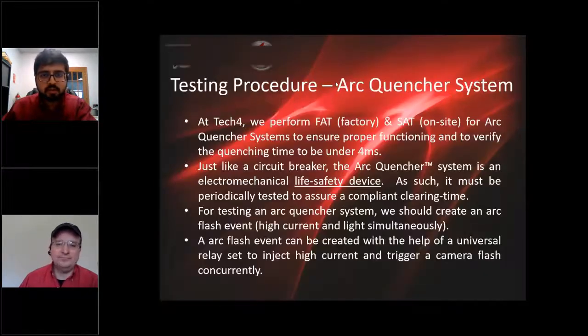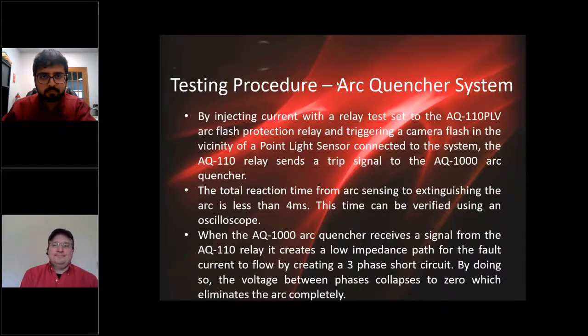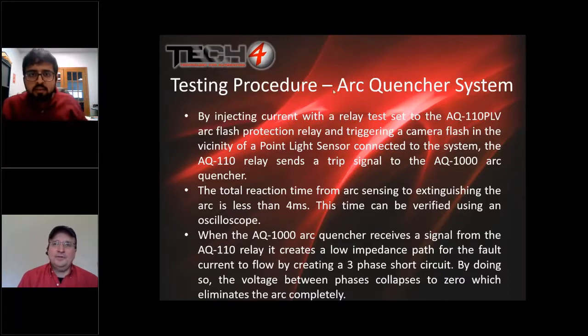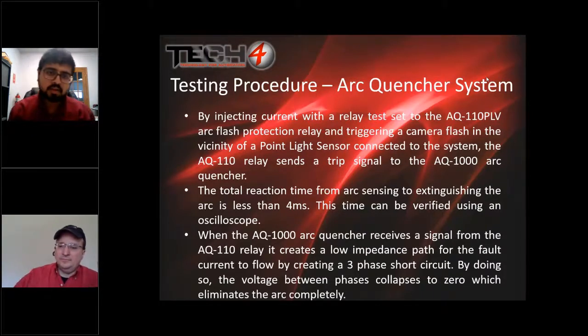Let's go back to the presentation. So I was talking about injecting current and using a camera flash to trigger the trip signal from the AQ110 relay to send it to the arc quencher. And we measure the time on an oscilloscope to verify it's under 4 milliseconds. Again, I've explained here how the arc quencher receives a signal from the relay and creates a low impedance path. It shorts the 3 phases, and by doing so, the voltage between the phases collapses and extinguishes the arc.